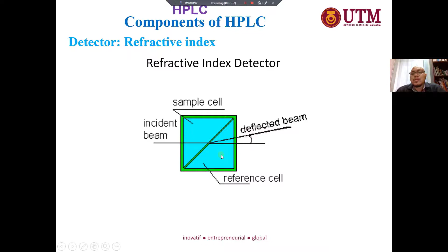Now the minus points. The RI can be affected by temperature, so you need to control the temperature carefully. Compared to UV and DAD for analytes with a chromophore, the sensitivity of the RI is lower. And for the RI, we cannot perform gradient elution. Why not?